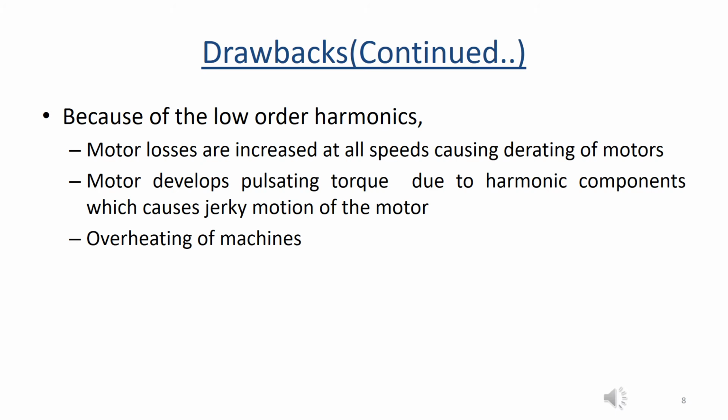Because of the lower order harmonics, we have three problems. One is the motor losses are increased at all speeds, causing derating of motors. Motor develops pulsating torque due to harmonic components, which causes jerky motion of the motor and overheating of machines.